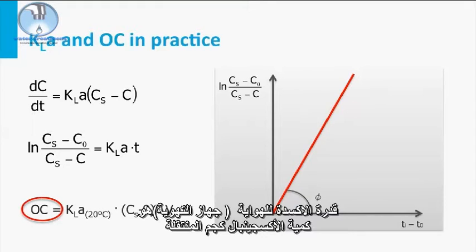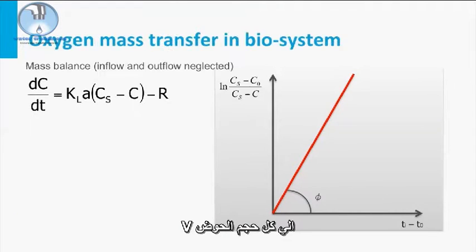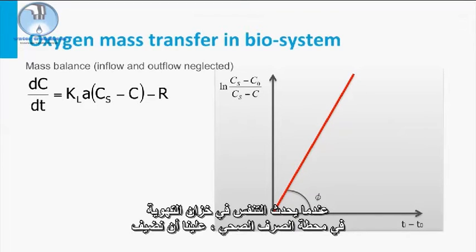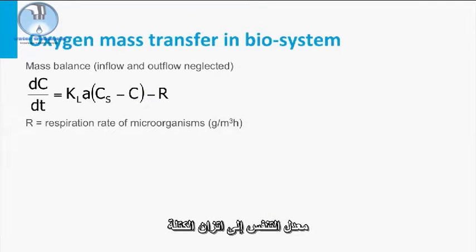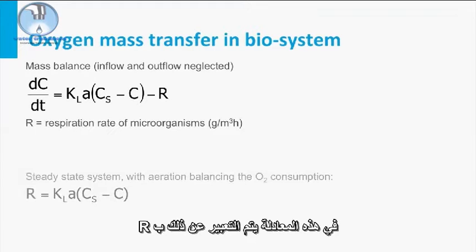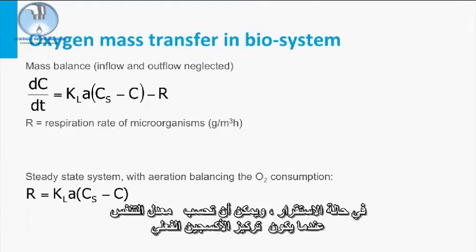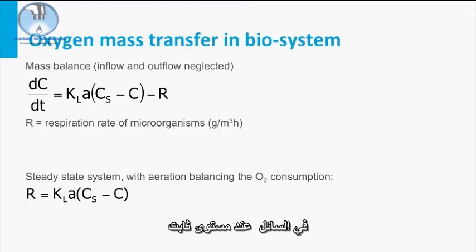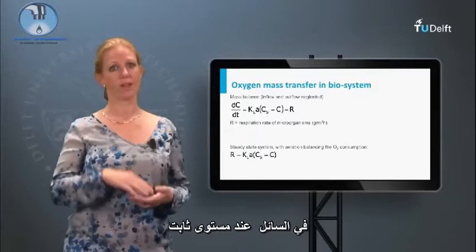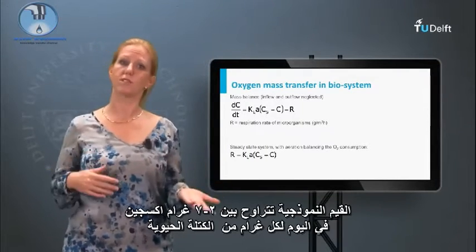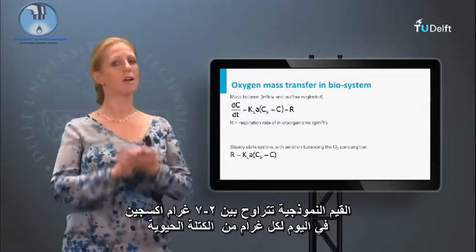The oxygenation capacity of the aerator is the quantity of oxygen in kilos transferred in the total tank volume V. When respiration occurs in the aeration tank of a sewage treatment plant, we have to add a respiration rate to the mass balance — expressed as R in this equation. In a steady state, the respiration rate can be calculated when the actual oxygen concentration in the bulk liquid is maintained at a constant level. Typical values vary from 2 to 7 gram oxygen per day per gram of biomass.